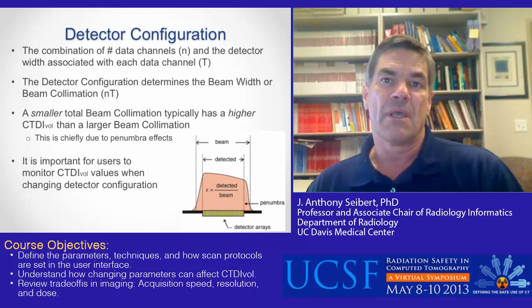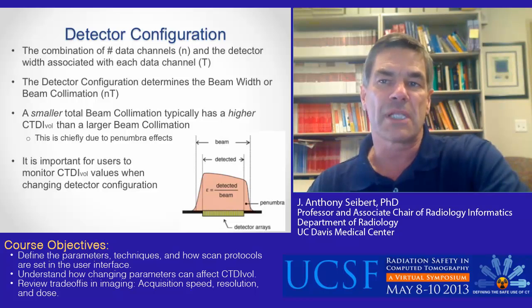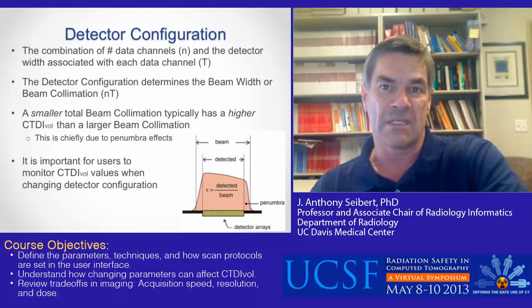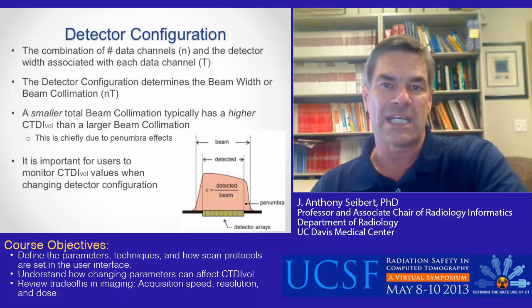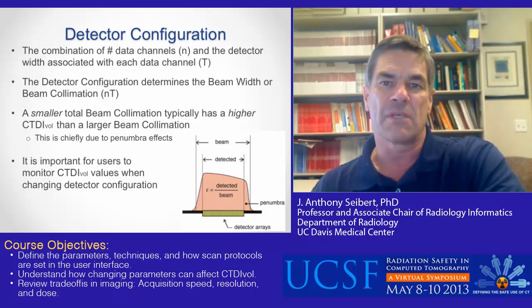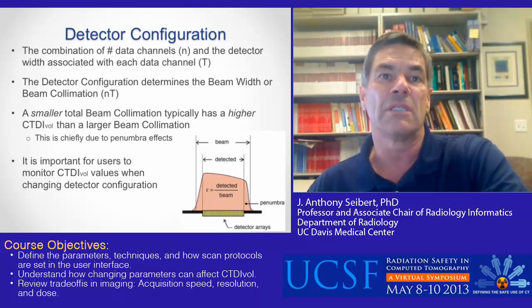Detector configuration: with multi-detector row CT scanners, there are many selectable combinations of data channels and detector widths associated with each channel. The detector configuration determines the beam collimation width, which is equal to the product of the number of channels N and the detector width T. The actual beam width is larger than the active detector array because of x-ray intensity variation in the penumbra. The efficiency of x-ray utilization is a ratio of the detected beam width to the actual beam width. In general, a smaller beam collimation has a higher CTDI vol than a larger beam collimation because the efficiency of detection is less. It is important to monitor changes in CTDI vol when changing the detector configuration.